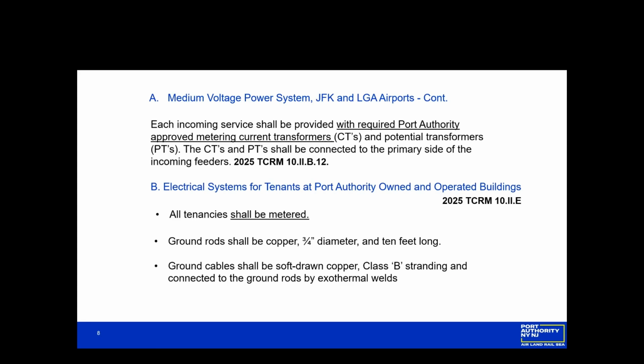Ground rods shall be copper and 3/4 diameter and 10 feet long. Ground cable shall be soft drawn copper, class B, stranding and connected to the ground rod by exothermic welds. Next.